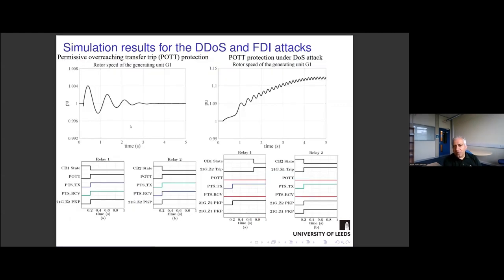Here we can see the outcome of these 2 attacks. So on the left-hand side, you can see the case where permissive overreaching transfer trip protection, which is one kind of communication-assisted protection, is implemented without considering cyber attack on the system. In this scenario, as you can see, the fault occurred at 0.2 seconds. And then because there was no attack, the POTT protection works correctly and cleared the fault immediately after its inception. And as you can see, the generator kept its synchronization with the rest of the grid, so it continued normal operation, basically.